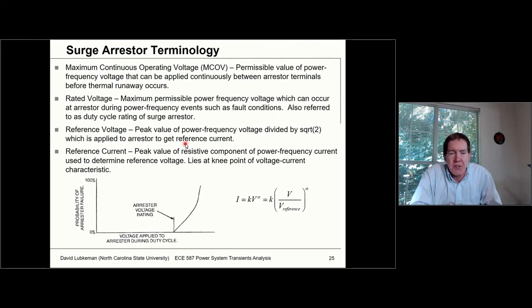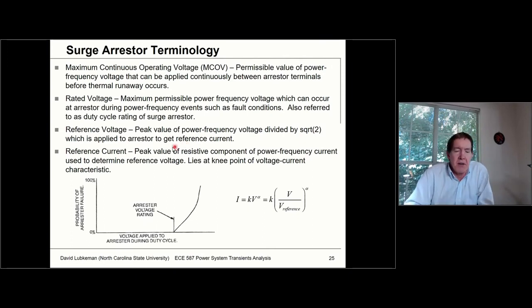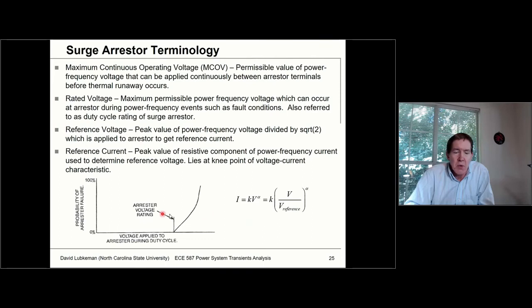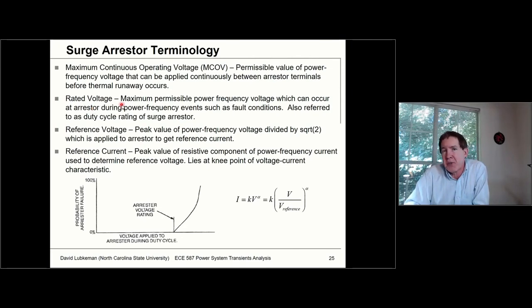There's also a rated voltage for the arrestor, a bit higher than MCOV. This is the maximum voltage during normal power frequency events — 60 Hz type events — such as fault conditions or ferroresonance. As far as IV characteristics, there's a reference voltage and reference current used for figuring out the I-versus-V characteristics. We must keep the voltage across the arrestor below these two values under normal conditions, including faults, otherwise we can actually destroy the arrestor in the field.